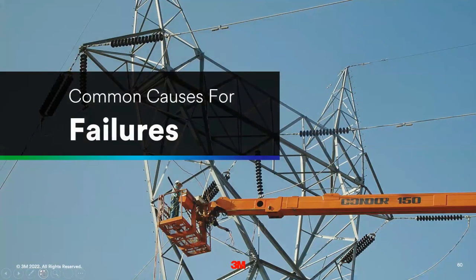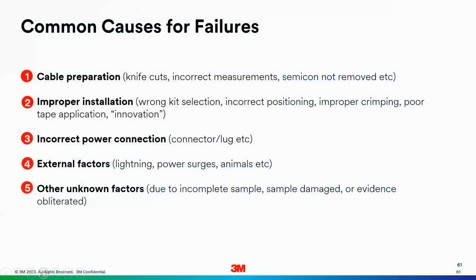So I'll go over these briefly, but just common causes for failure in a medium voltage cable. Most of the time, we have down in our headquarters in Austin a failure analysis lab, and customers will send in their dead bodies, splices, terms, elbows, basically cut them off and send them down there to be analyzed to find out where the point of failure was.